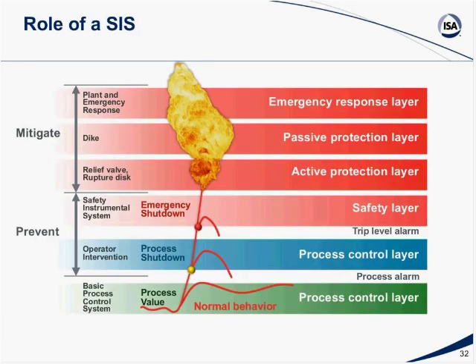So let's look a bit at the role of a SIS further. In this diagram, you would see a normal behavior where you have a process layer on the bottom, with the basic process control system in the process control layer. If a process is operating in a normal way, you would obviously see your PV parameters within the process control layer. But if your process parameters exceed above a certain value, that's where you see a process alarm, and it goes into the next step where the operator has to intervene. If the operator intervenes and brings the process back into control, then you don't need to go into the next level, which is the safety instrumented system, where the SIS comes in and prevents any kind of incident and brings your process back to a safe state.